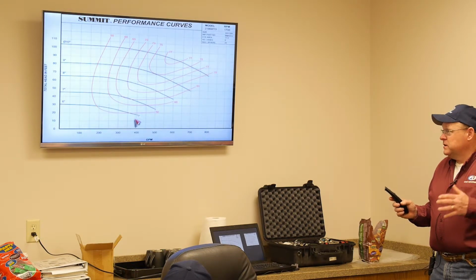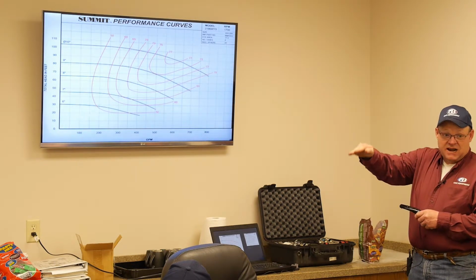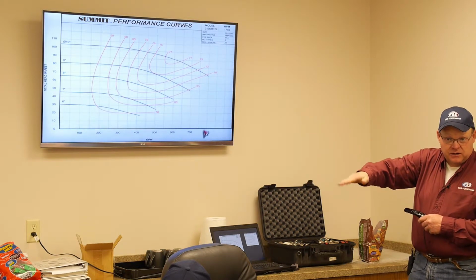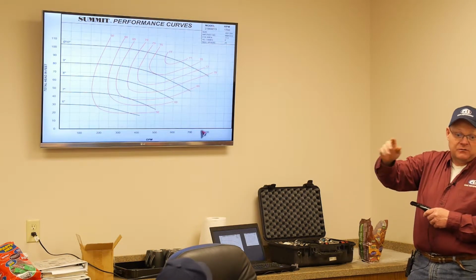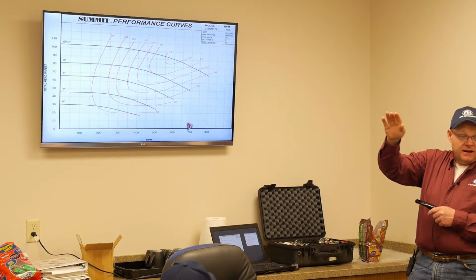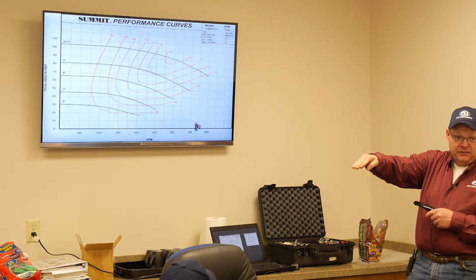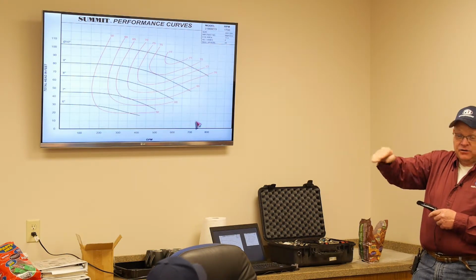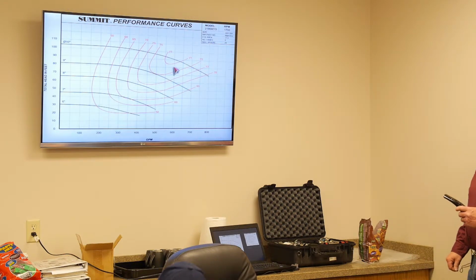Could be getting some vibration, but you're probably getting a huge amount of radial load. Remember, we're running close to shutoff. We're pushing down on that impeller. We're loading that inboard bearing, and we are starting to deflect the shaft, right? At near shutoff, okay?